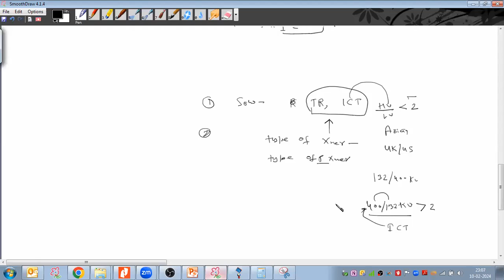Provided your system should be grid voltage, not any distribution voltage. So 132 kV is grid voltage and 400 kV is also grid voltage, so there is no source of harmonics here. So they can go with ICT even though the voltage ratio is more than 2 here, that single phase auto transformer.